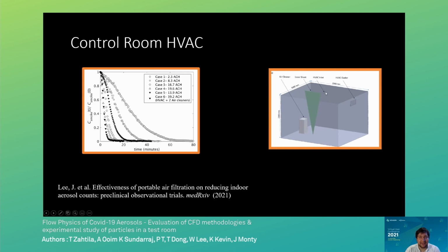and you only had a HVAC, so no air cleaner for a moment, how long would it take for the HVAC to remove those particles from your system? If you're a bystander standing in this room, and you wanted to have half the number of particles in this room as there were when we started the experiment, you'd need to wait approximately 20 minutes.